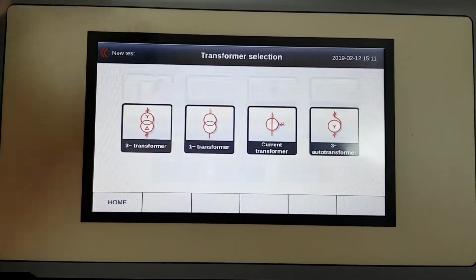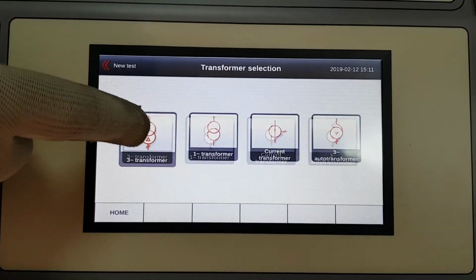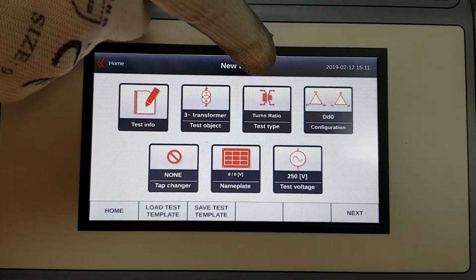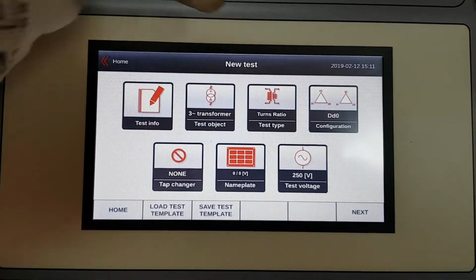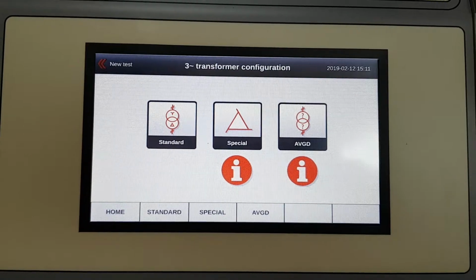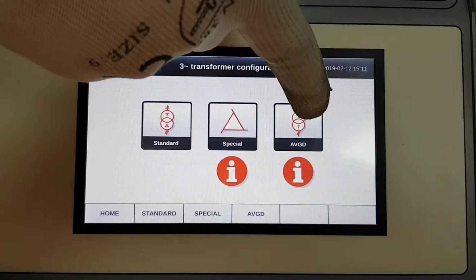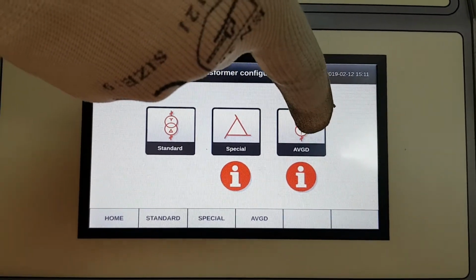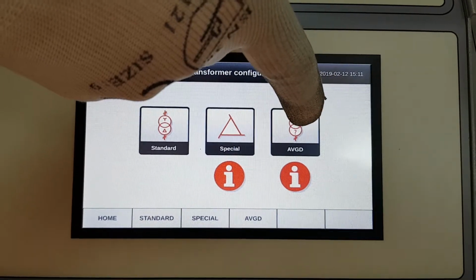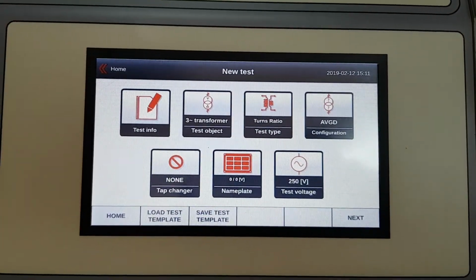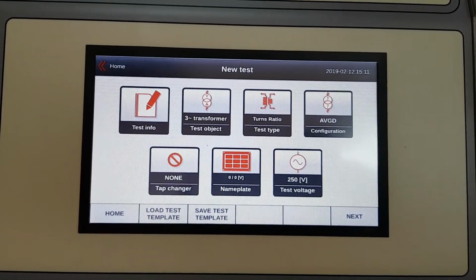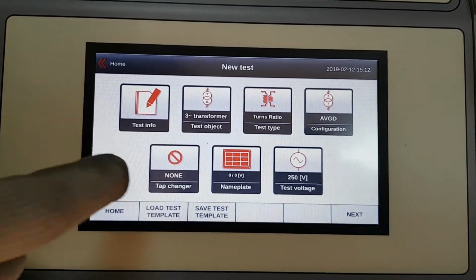Then we need to select the test object type, which is in our case three-phase transformer. We're going to do the turns ratio test, and for the configuration I'm going to choose the AVGD, which stands for automatic vector group detection. So TRT400 is going to automatically detect vector group of the transformer under test.